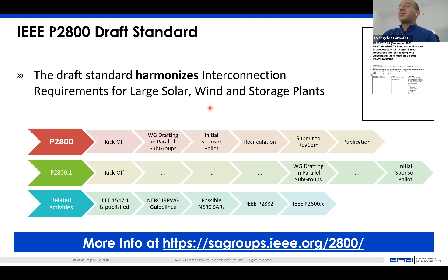What this standard does is describe technical minimum capability requirements and performance requirements for these inverter-based resources. Without going into details, it discusses what their frequency response should be, what their reactive power and voltage control capabilities should be, and it also covers modeling, model validation, and testing.